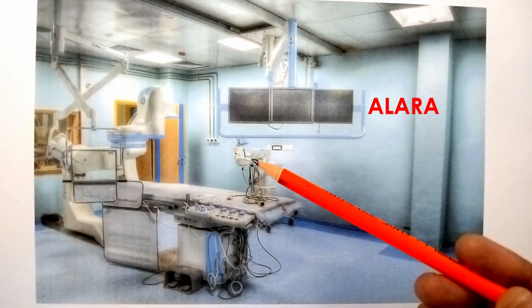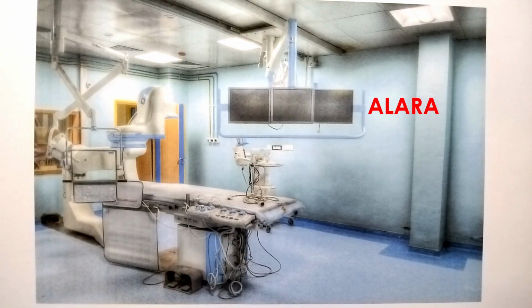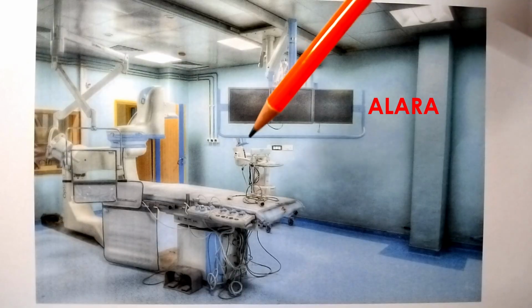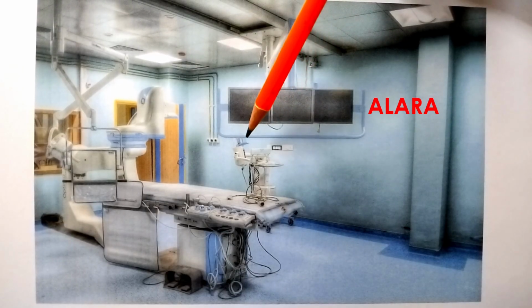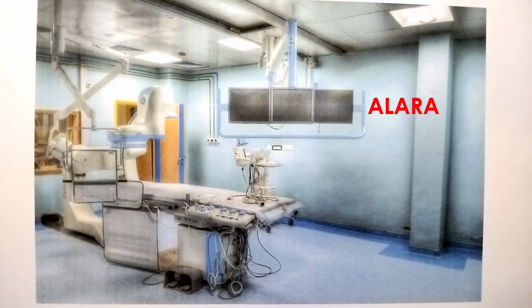Then this is a pressure injector used to give injections into arterial or ventricular chambers, because arterial pressure is high, so you need to overcome it with a pressure injector, and it will also be timed. That is, it can deliver so much volume in so many seconds. That can be set. That is the pressure injector. Coronary angiography is usually done with hand injection, while ventriculography and aortography will be done by pressure injectors.